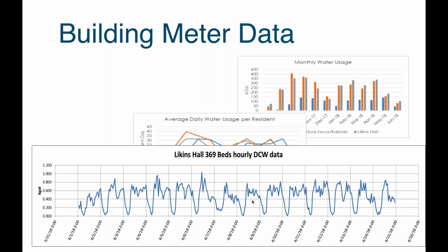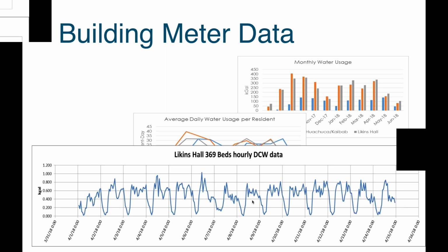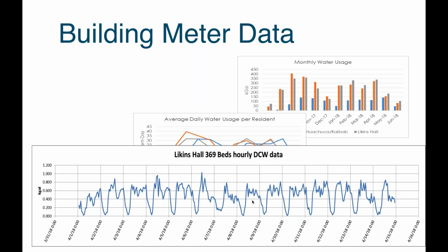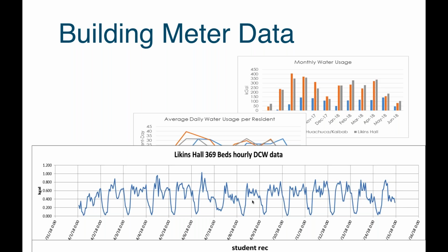That's actually hourly data, which is great for tracking leaks and anything happening inside the facility. We've seen cases where you first look at monthly data and notice a building behaving differently this February than last February. Then you dig into this level of detail and see why: a valve not closed, a leak, and you can really see it hour by hour in this data set.